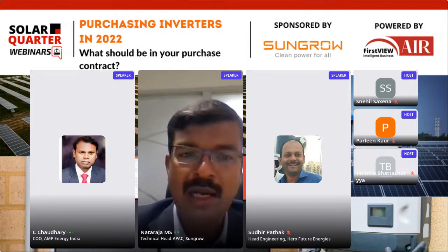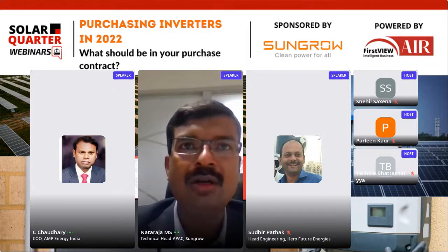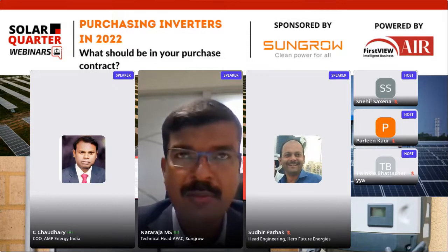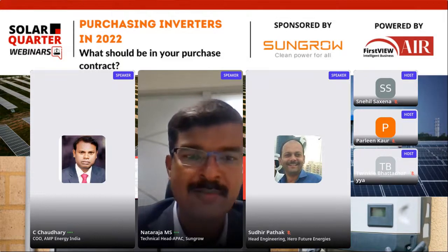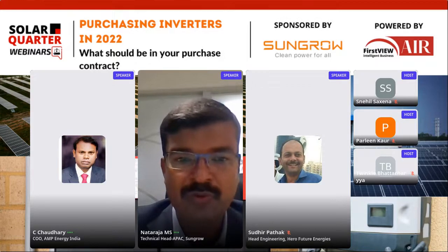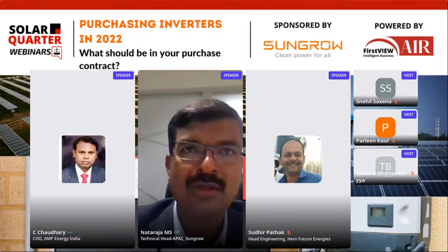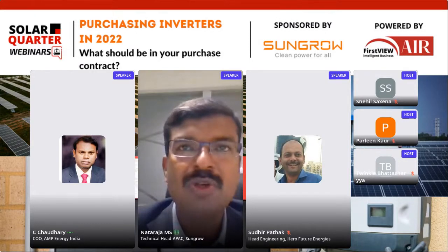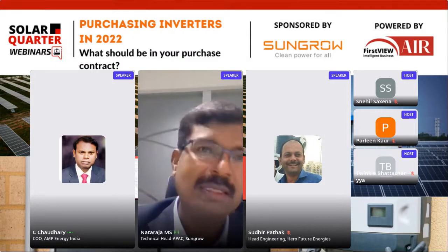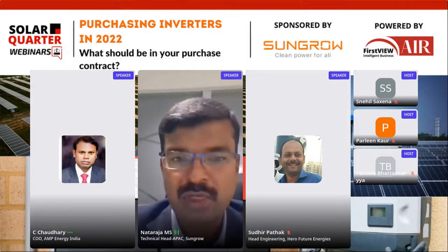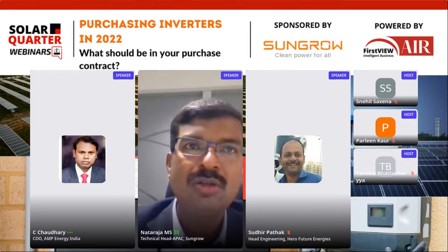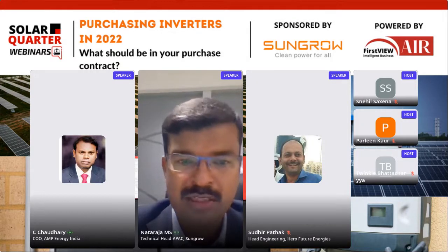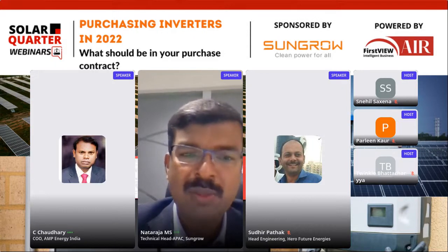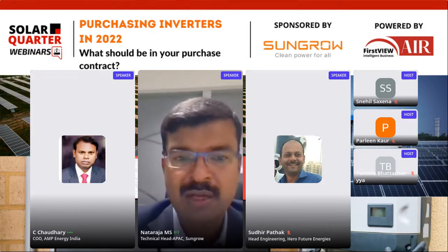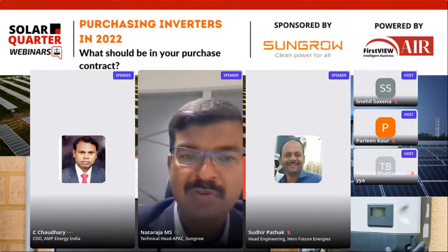Basically, you will have one dedicated breaker or bus bar where you can tap your DC to DC and battery connections. For example, if I take our inverter, right now whatever we are selling is about a 2 MPPT version, and this 2 MPPT version will also have an interface for BESS. Even a 5 megawatt inverter will also have this BESS interface. In this case, only a little more has to be spent by developers because some hardware needs to be added, for example a bus bar and maybe a breaker, as part of the inverter for BESS.